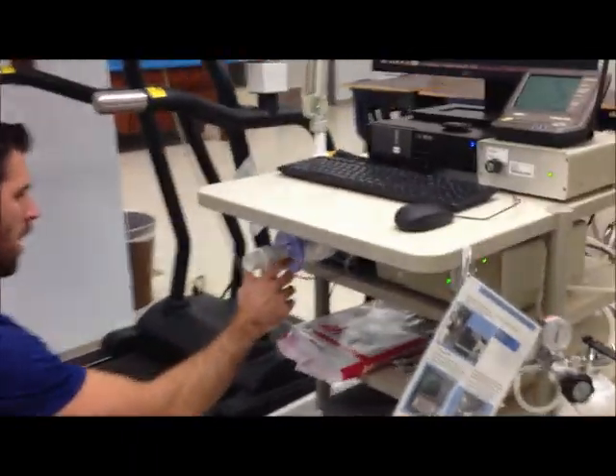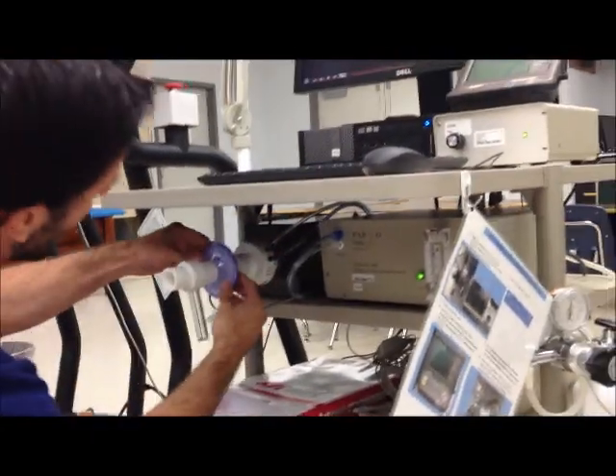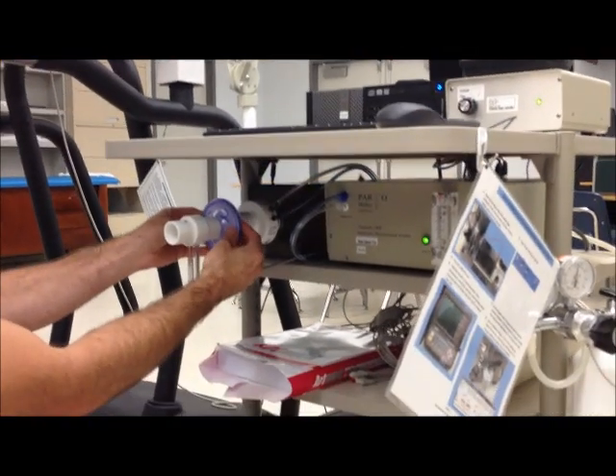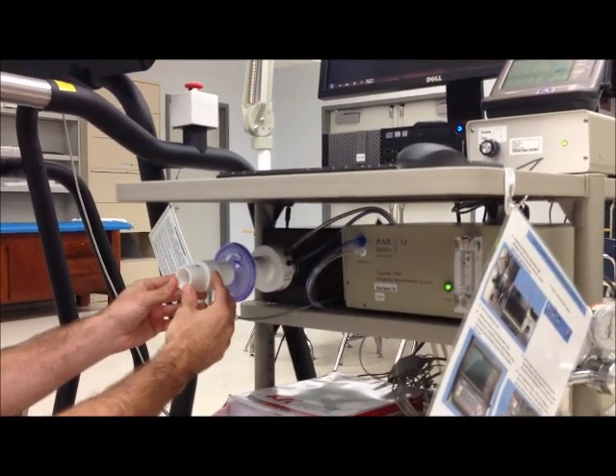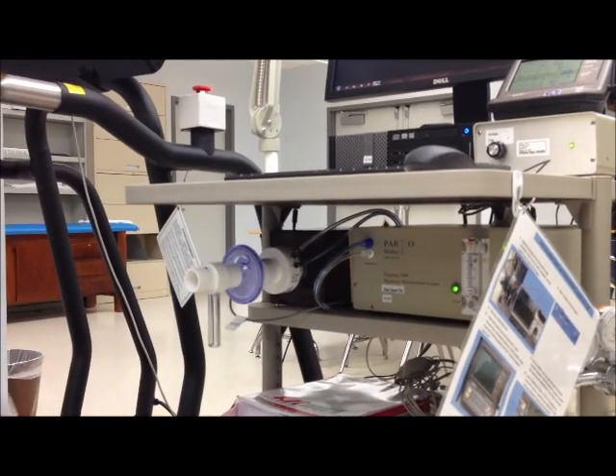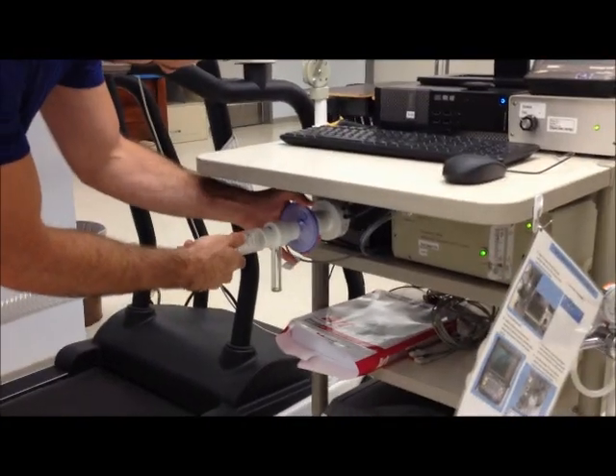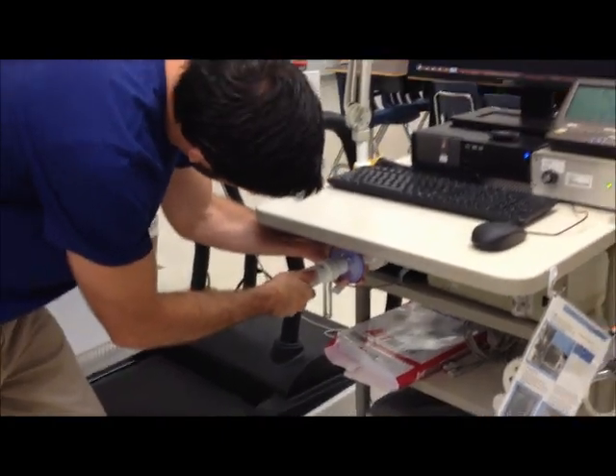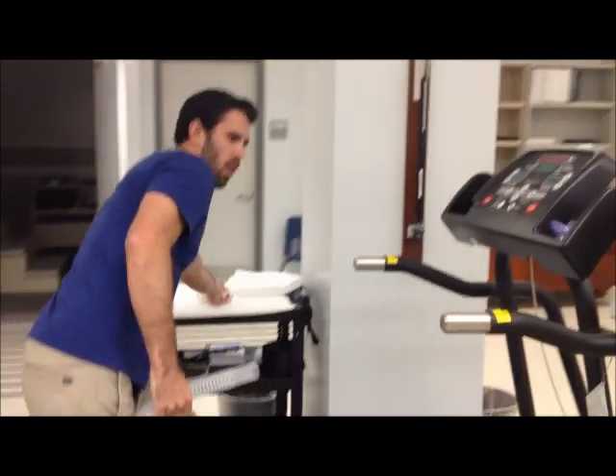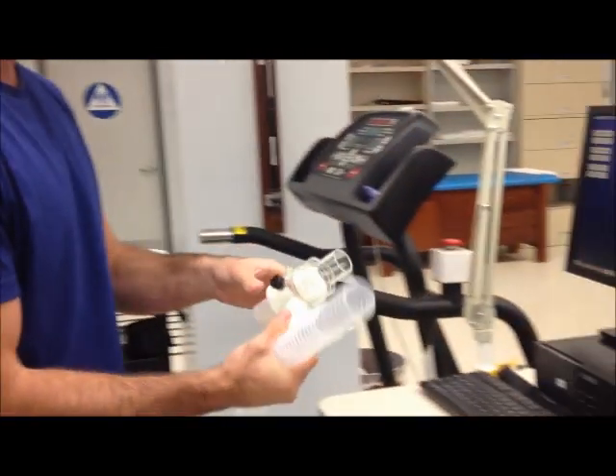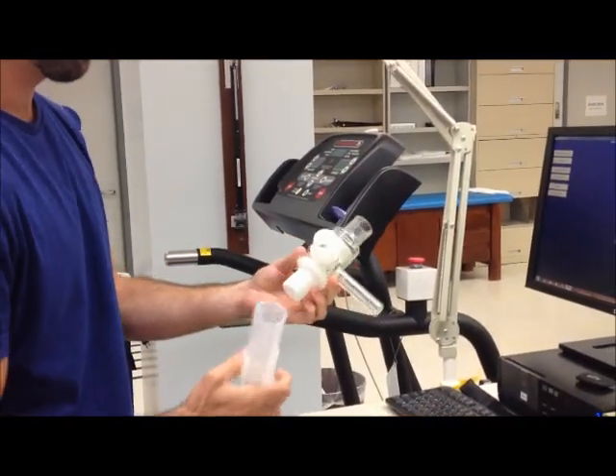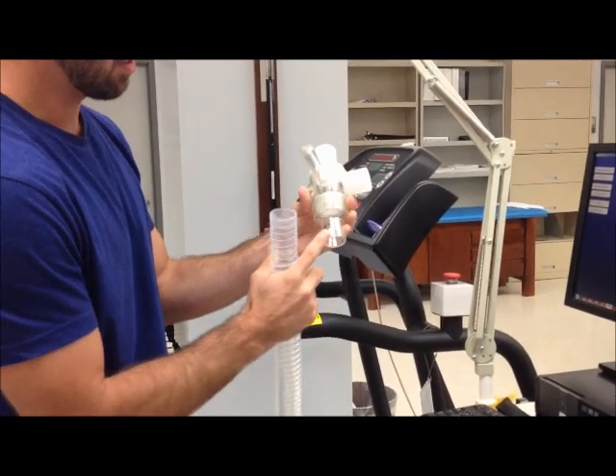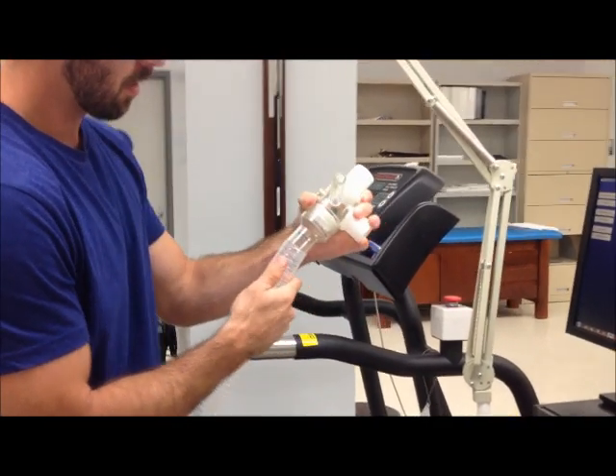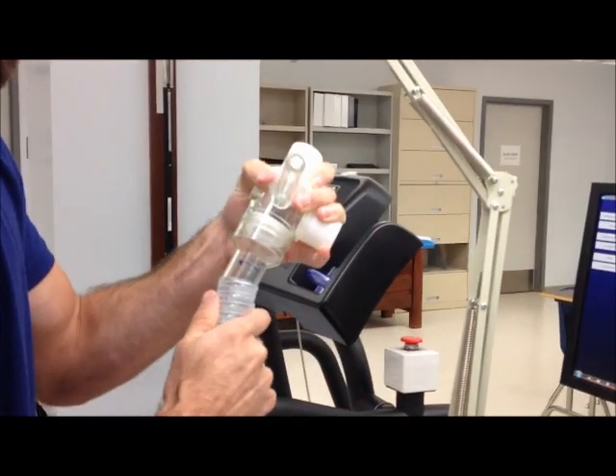Flowmeter calibration, you're going to make sure that you have all your equipment set up correctly. This is the Pneumotach. Make sure you have that connected to a moisture filter, connected to a liquid trap. And then from there, we're going to connect the tube to that assembly, and we're going to run that to our two-way breathing valve. You connect this to the clear side that's with the blue line.